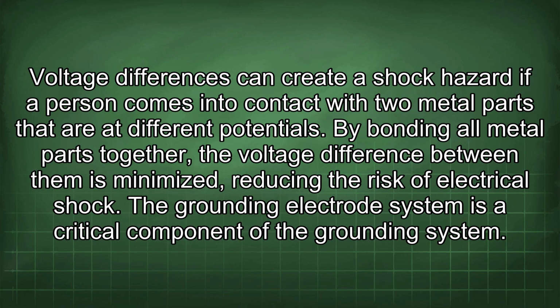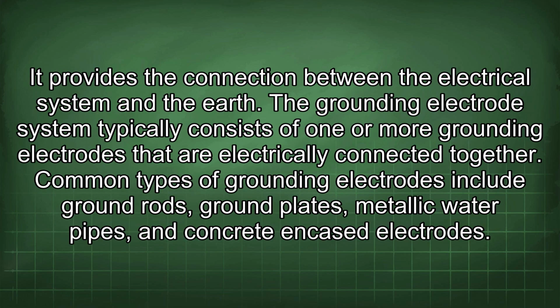The grounding electrode system is a critical component of the grounding system. It provides the connection between the electrical system and the earth. The grounding electrode system typically consists of one or more grounding electrodes that are electrically connected together. Common types of grounding electrodes include ground rods, ground plates, metallic water pipes, and concrete encased electrodes.